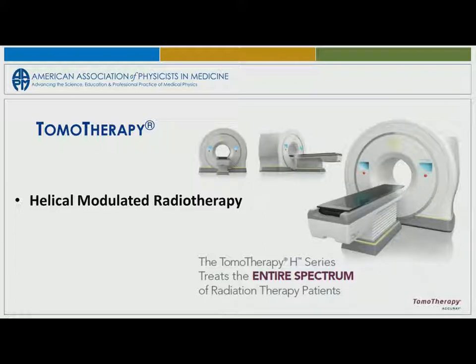If you go tomotherapy or helical modulated radiotherapy, obviously you have a built-in primary barrier because the machine is on basically like a CT scanner. So you don't really have a primary barrier. That's what makes those machines much easier to shield. On the other hand, you have really thicker secondary barriers.